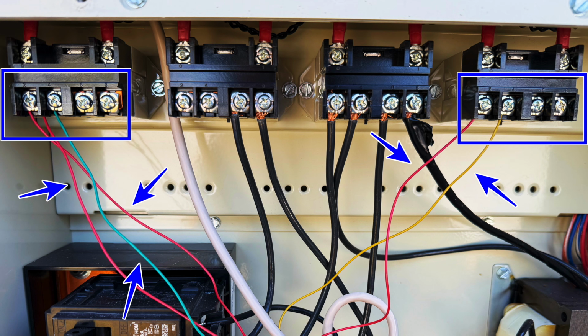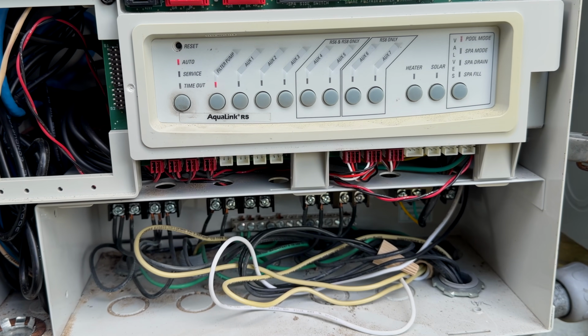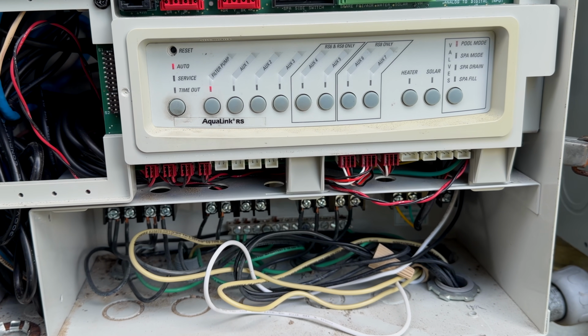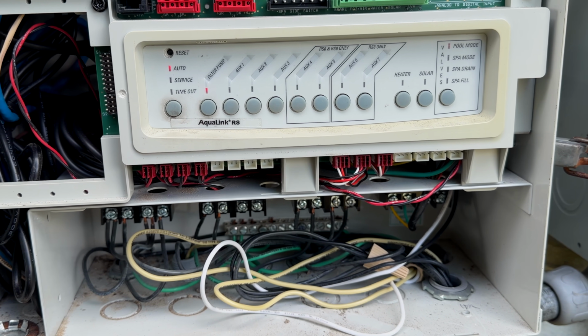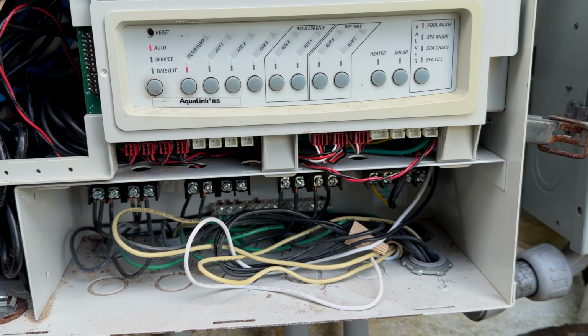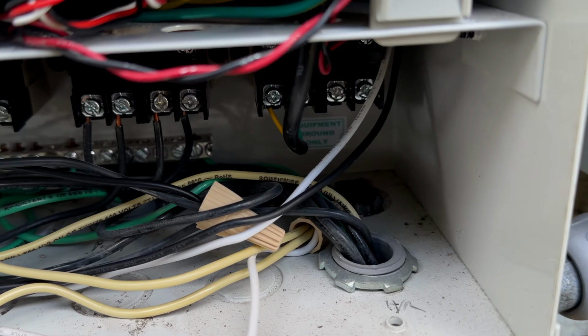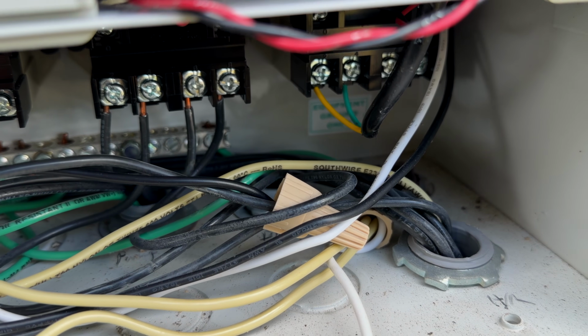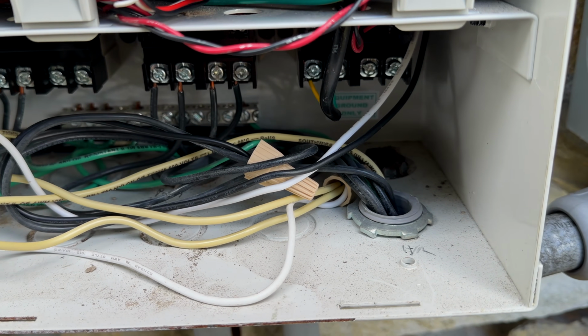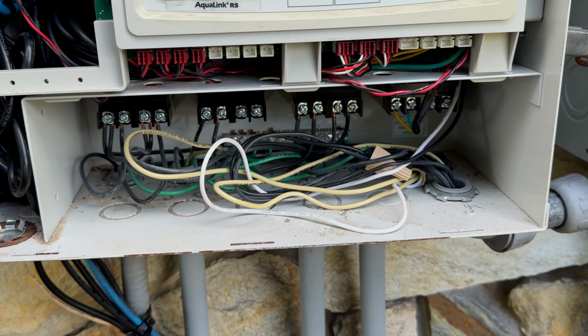They had a communication wire with 8 different wires, and in order to get the superflow to do different speeds, you'd have to wire those to specific open relays in the high voltage area. So zero difference there. It's just you don't ever want to put a high voltage line there, because you will absolutely destroy whatever low voltage component is tied to that relay.